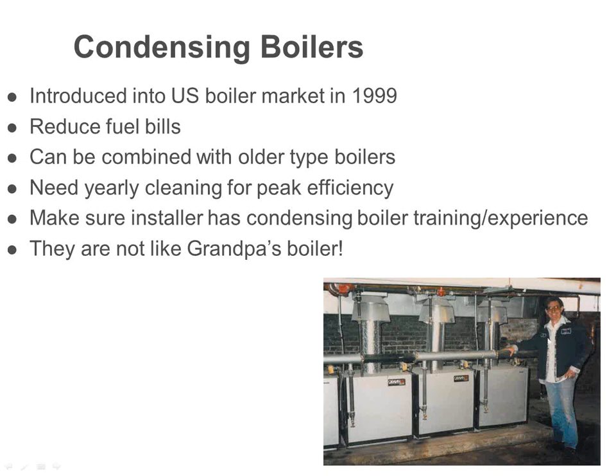A couple things with condensing boilers, though. They do need to be cleaned on a regular basis if you want to maintain that high efficiency, and this goes for a furnace or any piece of equipment. If you don't maintain it, from day one you're going down. Other thing with condensing boilers: if you don't know how to do it, get some training. If you put in a new condensing boiler just like Grandpa did, you will have issues, guaranteed. They do not pipe the same way. They have other controls on them. There's a lot of different stuff here. This is not your old cast iron boiler, water in, water out, okay? So do get some training.